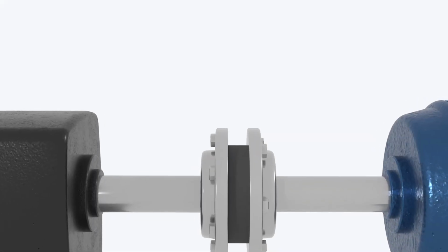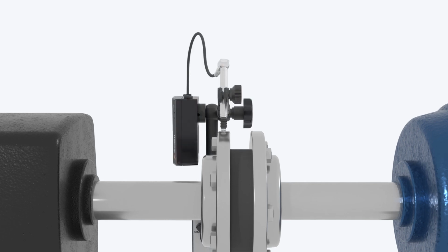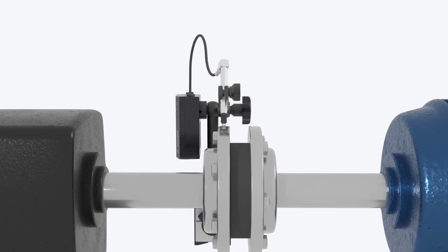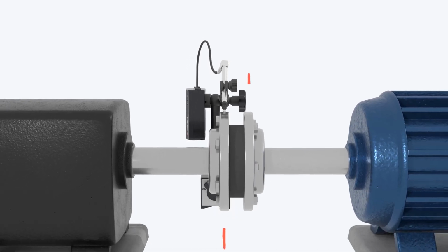When measuring runout, the probe base should be mounted to a fixed point, such as the base of the machine or any other fixed position. We recommend that you first check for runout at the hub or the rim of the coupling, because there you will pick up both eccentricity and bent shaft.